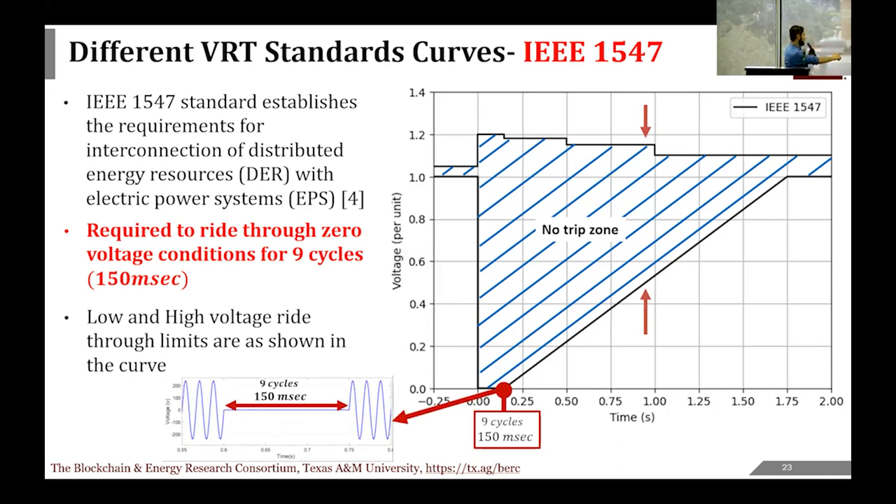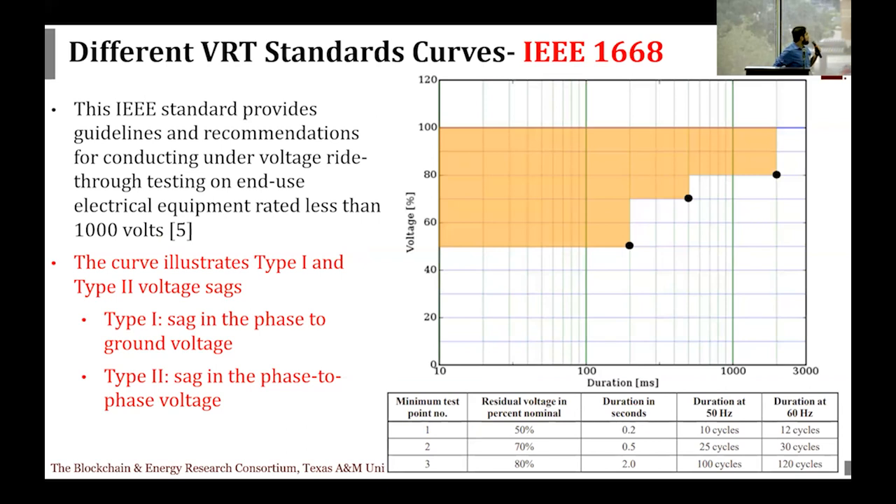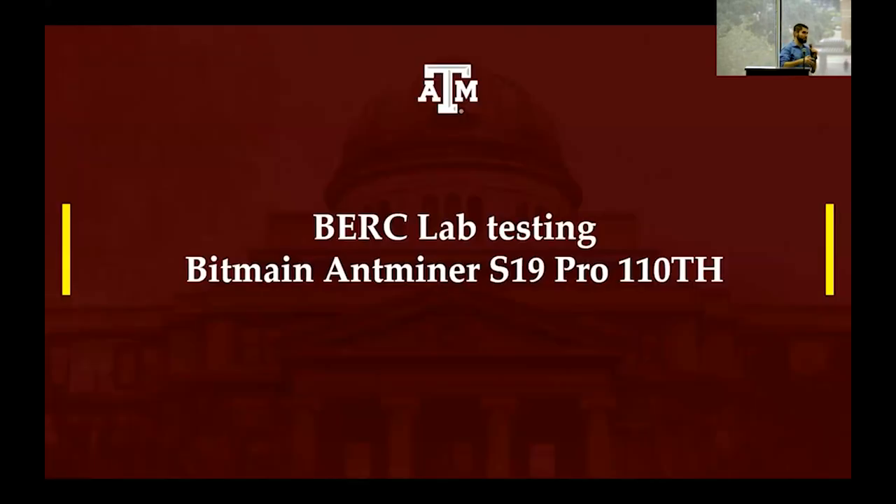The 9-cycle zero-voltage requirement in IEEE 1547 means the machine, when experiencing a drop to zero voltage, is expected to ride through it and remain continuously connected to the grid. The IEEE 1668 standard covers loads less than 1000 volts, and its table shows requirements for phase-to-ground and phase-to-phase sags: at 50% voltage, ride through for 10 to 12 cycles; at 70% for 30 cycles; and at 80% for about 100 to 120 cycles. After covering these different standards, we wanted to see how the miner compares to them.